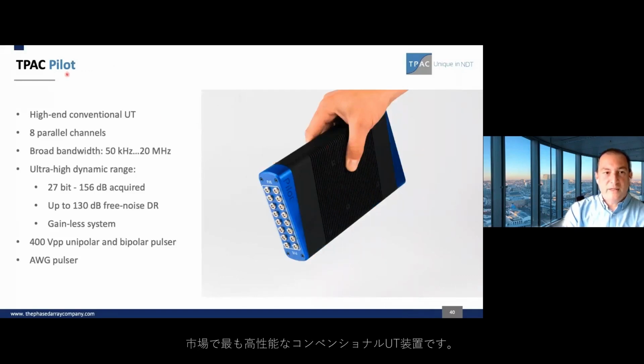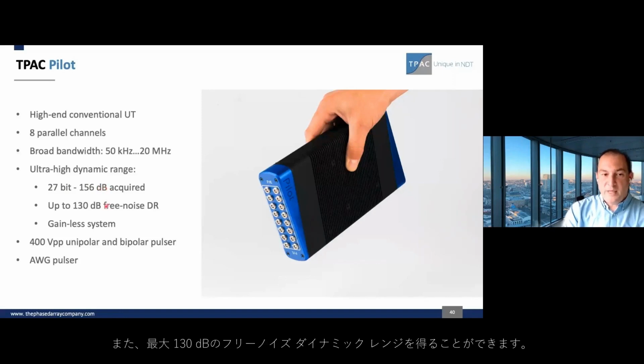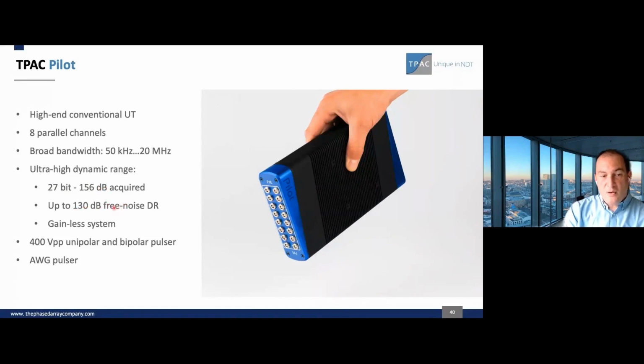The bigger version is called Pilot. It's the highest end conventional UT in the market. It has 8 channels, again working in parallel, and a broad bandwidth going from 50 kilohertz to 20 megahertz. This broad bandwidth allows for a wide range of applications, including air-coupled UT. This module provides a very high dynamic range. We can acquire the data with a 27-bit resolution, which means 156 dBs of information acquired. We can obtain up to 130 dBs of noise-free dynamic range. And all this makes it unnecessary to use gain control, so we can acquire the signals without worrying anymore about the gain setting. We also have 400 volts unipolar and bipolar pulsar, and as an option, we can also include an AWG pulsar.